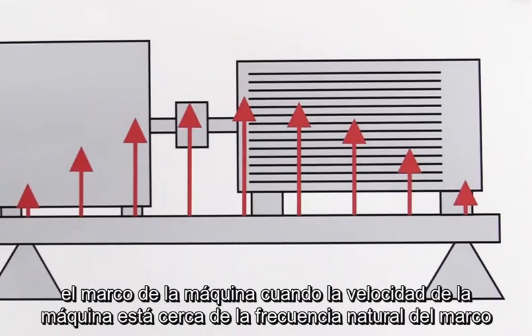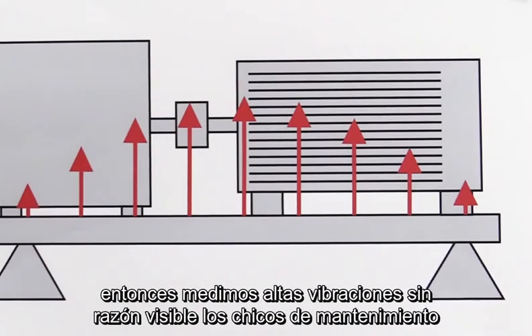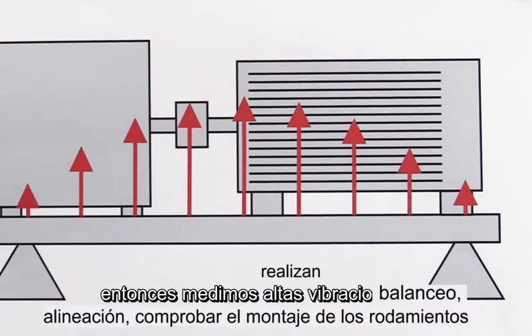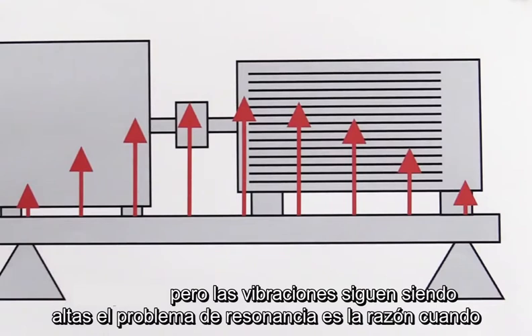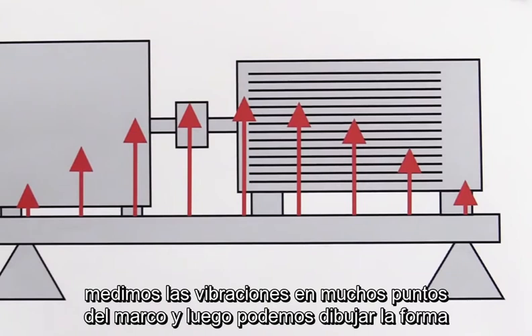We most commonly encounter resonance problems on a machine frame. When the machine speed is near the frame's natural frequency, we measure high vibrations without a visible reason. Maintenance technicians usually perform all standard procedures like balancing, alignment, and bearing mounting checks, but vibrations still remain high — the resonance problem is the reason. When we measure vibrations at many points on the frame, we can draw the shape of the frame, where each arrow is proportional to the vibration level at each point.